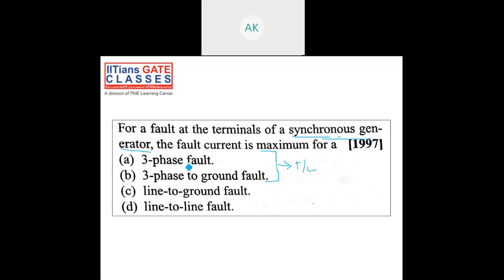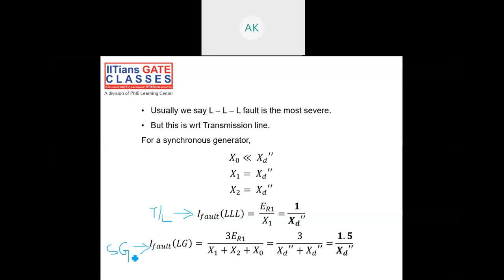For a synchronous generator, the zero sequence value is very small, very negligible. Then the values of X1 and X2 are the same as the subtransient reactance. So if you calculate the fault current for an LLL fault or LLLG fault, it is E by X1, which is 1 by Xd dash, right? If you look at an LG fault, it is 3E divided by X1 plus X2 plus X0. So it will be 1.5 by Xd dash, which is higher. So for a synchronous generator, this is higher. But when it comes to a transmission line, this X0 value is not negligible. It's actually pretty strong, making this value smaller than this value. So remember this: for a transmission line, the highest fault current will be for an LLL fault, and for a synchronous generator, the highest fault current will be for an LG fault.